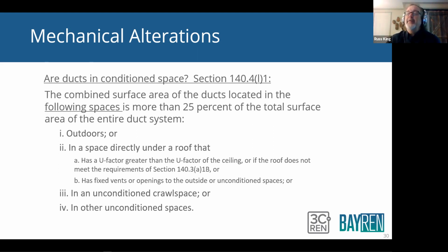If it's in a space directly under the roof, and this roof has a U-factor greater than the U-factor of the ceiling, in other words, there's less insulation at the roof than there is at the ceiling, or if that attic is ventilated, has turbine vents in the ceiling or eave vents or gable end vents or something like that, that's considered unconditioned space. If it's in an unconditioned crawl space of a building, you don't see that as much in commercial buildings as you do in residential, and then last but not least, any other unconditioned spaces. So if more than a quarter of the ducts are in one of these spaces, that triggers duct sealing and duct testing, okay? The 25% is the number they determined makes it cost effective to seal the ducts. What that means is 75% of the ducts are in conditioned space and only a quarter are outside. Even at that threshold, it's cost effective to seal those ducts.